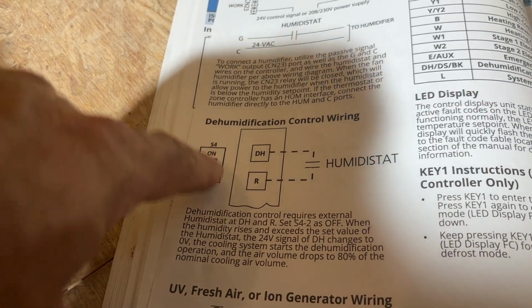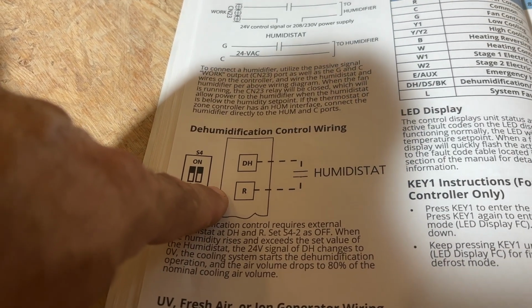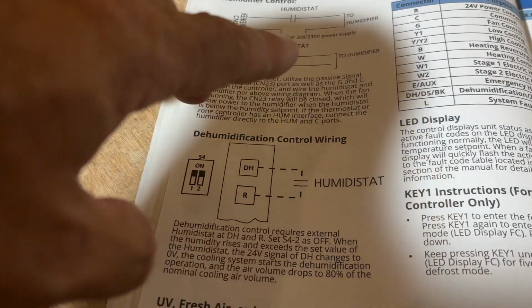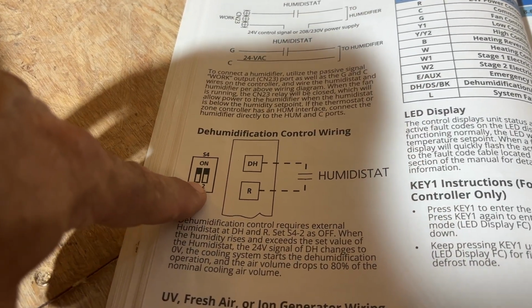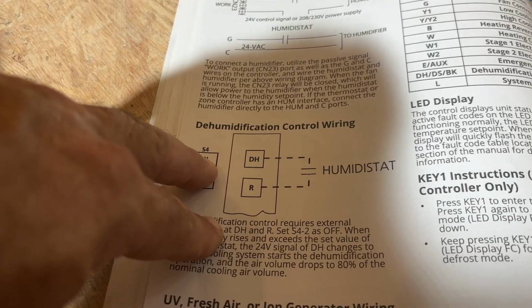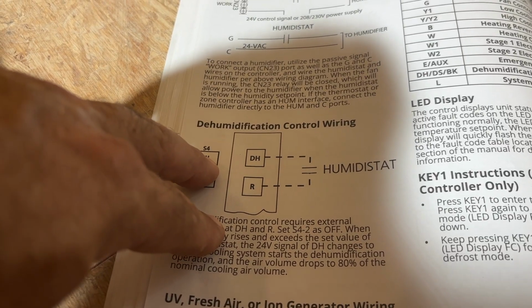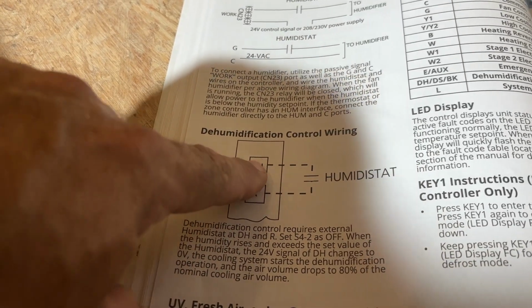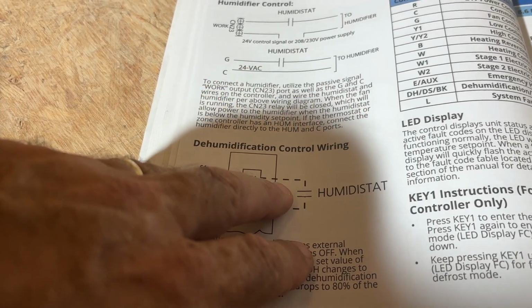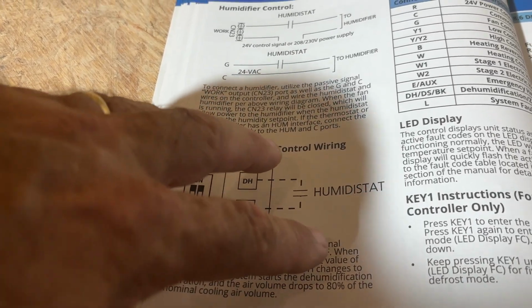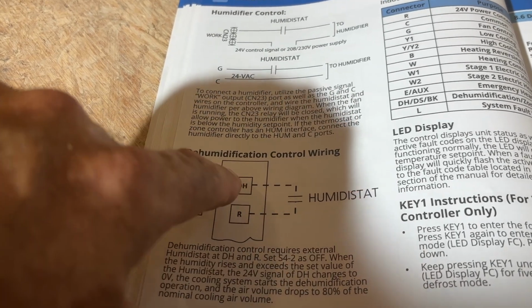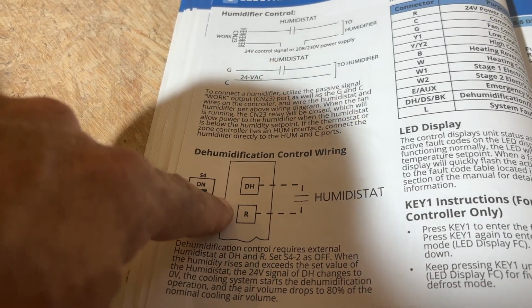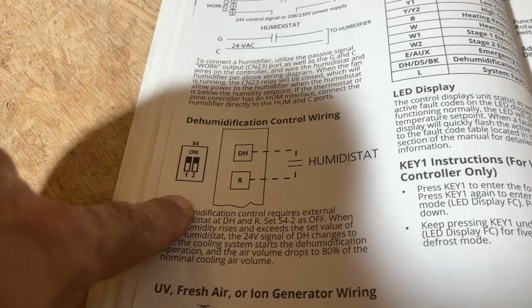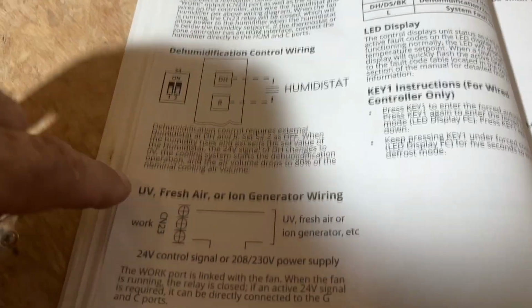Dehumidification control wiring. This is very similar if you want your humidistat to control your air handler, your VersaPro, and run it kind of like a mini split where you run it in dry mode. That's what this is. We're not going to do that because we have the whole home dehumidifier, and that's going to do a much better job than the humidity control function on this unit. So we're going to omit that.